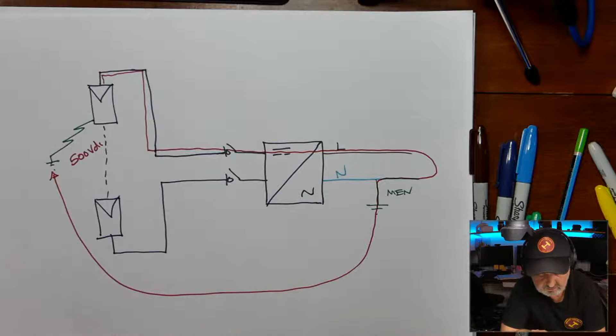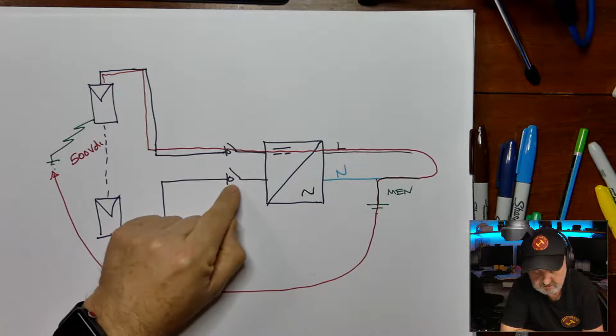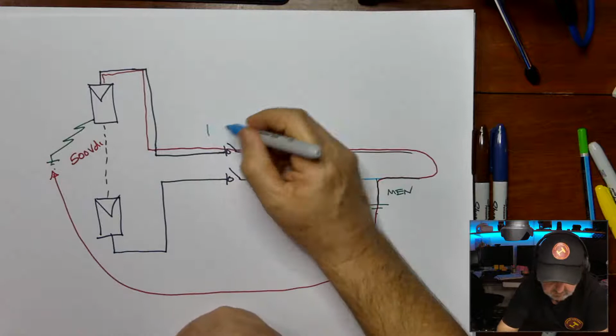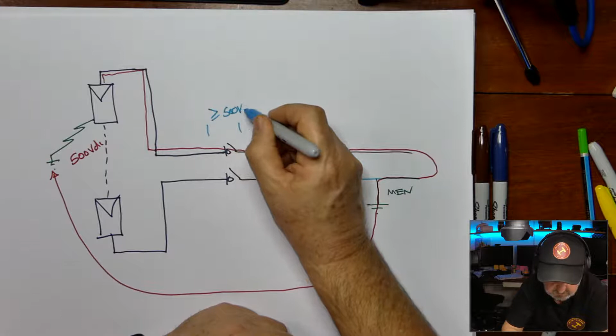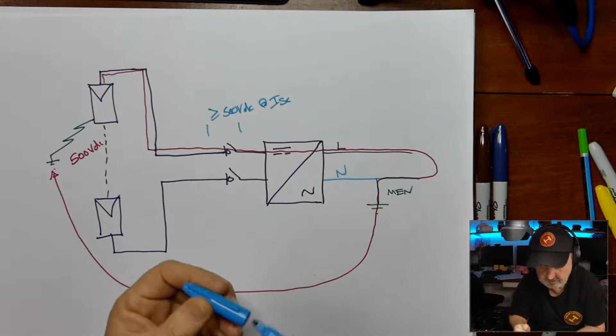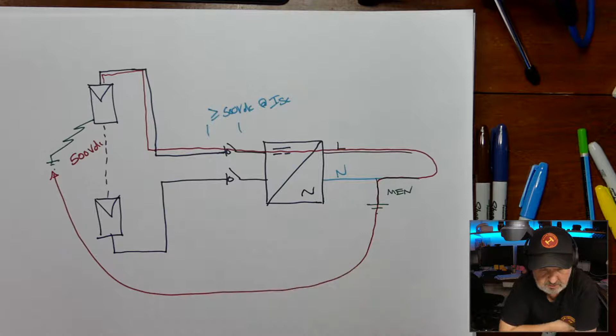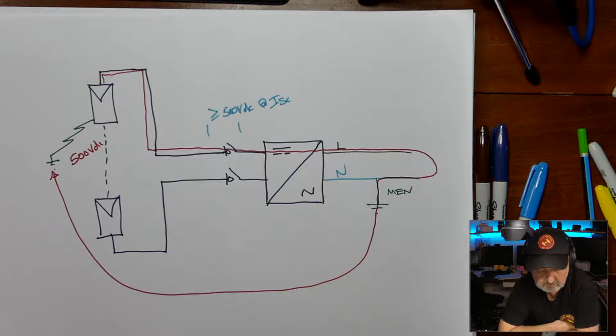When you go to remove that fault and open the DC isolator at the inverter, the PCE, you're only going to be interrupting that current on one switched leg. That means the voltage rating of this product across one switched leg needs to be greater than or equal to 500 volts DC, at whatever the current of the array is. Many products are rated when both poles interrupt the current, so you've got to look carefully into the voltage rating of the product to make sure you've selected the right one. I hope that answers your question.